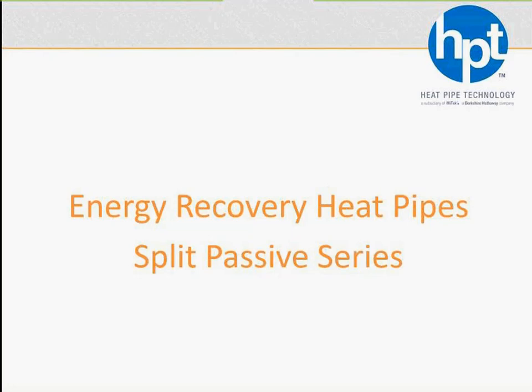The most important thing, I should mention, is to keep those coils or heat exchangers clean. Put filtration ahead of them when it comes to energy recovery, ahead of the exhaust, and you'll have filtration ahead of your supply anyway. But just make sure, as design engineers and manufacturers, that you have filtration ahead of the exhaust side of the energy recovery heat pipe, be it the standard one-piece heat recovery module or the split passive, which we'll be talking about shortly. Any other questions? Good. Moving on.